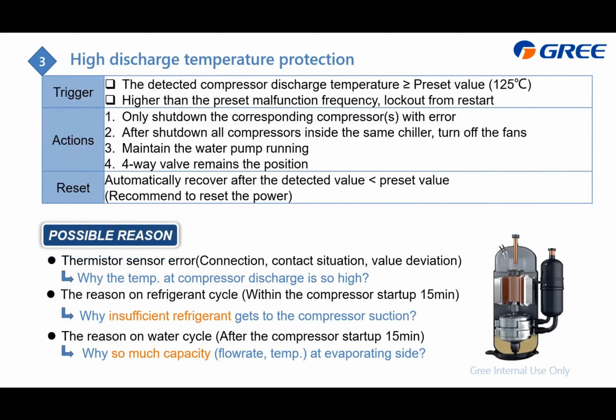And the next is the high discharge temperature protection. Actually, this one is very similar to the last one, the low pressure protection, in that the compressor cannot intake enough refrigerant. For this one, first it will of course lead to low pressure, right? And next, there's not enough refrigerant to cool the compressor down, which also leads to a very high compressor discharge temperature. Just like in this picture, the refrigerant is inserted from here, and then this is the compression chamber. After that it contacts the coils, and the coil is the hottest part inside the compressor. When the refrigerant goes through it, it cools the coil down and also becomes very hot. So if the detected temperature here is higher than about 125 degrees, it will also lead to this error.